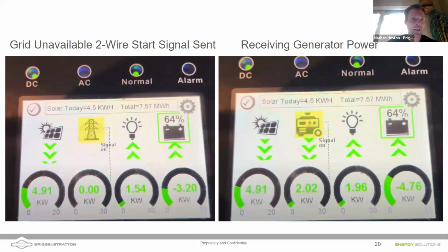Yeah, so what we're looking at here is the signal that gets sent. Right now you're seeing that there's a grid down situation and a signal is being sent to start up the generator. The line that's dropped down from the yellow grid means we don't have grid present. Once that generator comes on, you can set the qualification time. I believe mine's set at 30 seconds. Once that signal from the generator qualifies, you can have that come in and cover loads. What you're looking at there is 2 kilowatts of load. That generator is set up to prioritize covering the loads, and that extra solar power is being used to charge the batteries there.